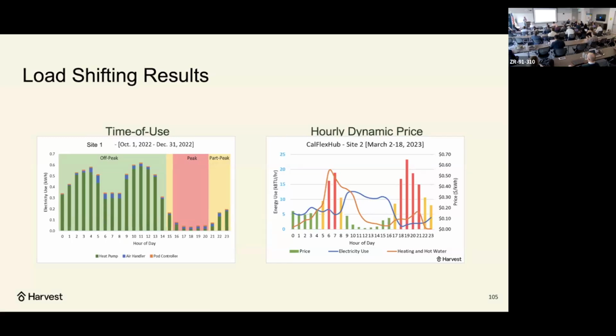On the right is hourly dynamic price response as part of the CalFlexHub cycle 2, where you can see the prices varying, with peak signals in the morning and evening. The color of the bars represents price on the second chart. The orange curve is thermal demand, both heating and hot water, and the blue curve is when that demand was reshaped using thermal energy storage. We could shift about 90% of the load, both space and water heating, on time-of-use, and on dynamic price, because it's got two peaks, it's about 70% of the load on a daily basis.